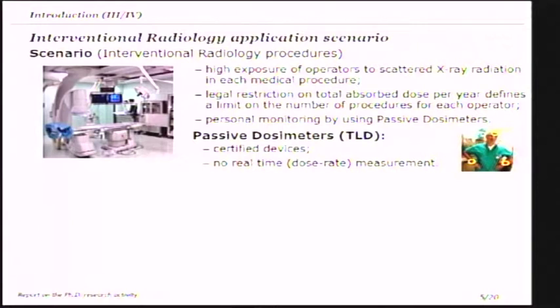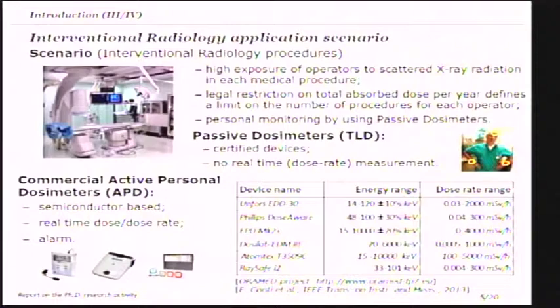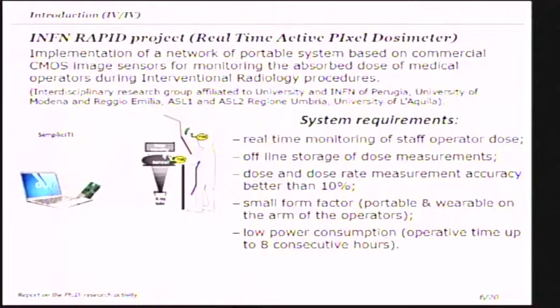The monitoring scenario is the interventional radiology procedures, and the attention was focused on the operator instead of the patient, because medical operators are exposed to scattered x-ray radiation during their work activity. Currently the monitoring of the absorbed dose is performed by using passive dosimeters that cannot provide a real-time measurement. In order to reduce the total absorbed dose, some active personal dosimeters are available on the market that can provide a real-time measurement of dose and dose rate, but in the ORAMED project in 2011 these devices were analyzed and some limitations were highlighted. In this context we want to implement a network of dosimetric systems.